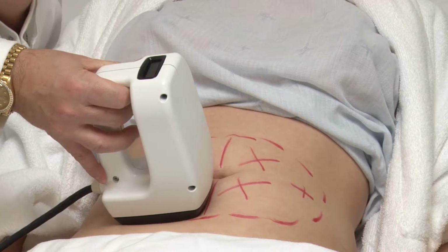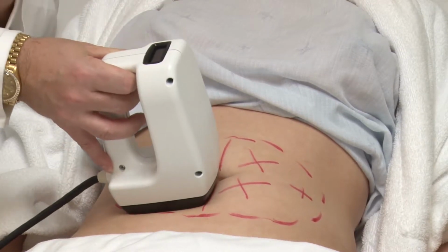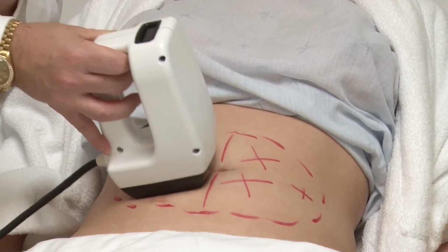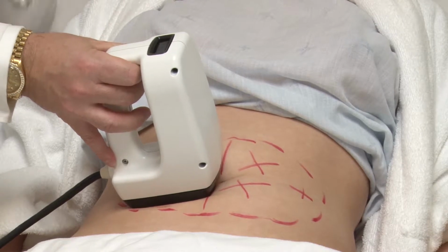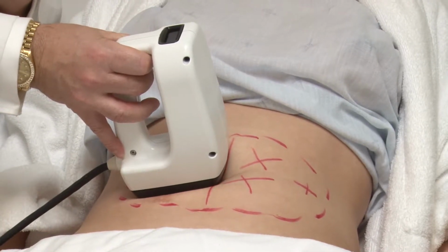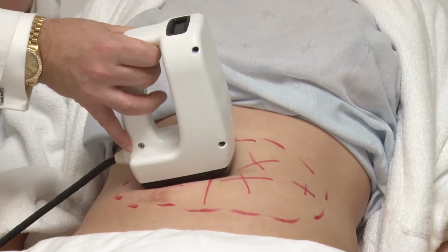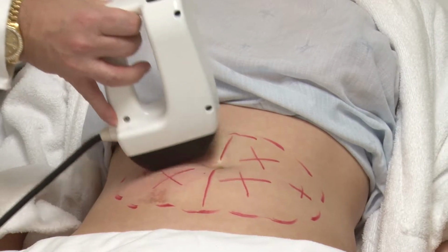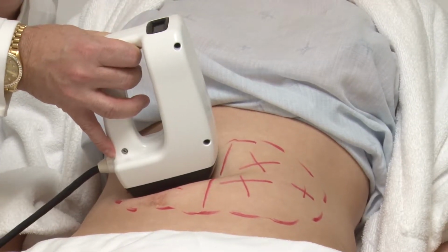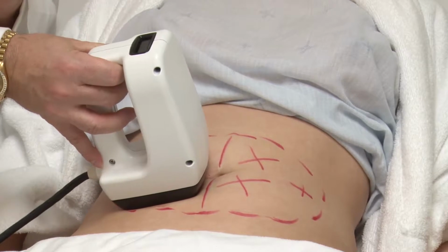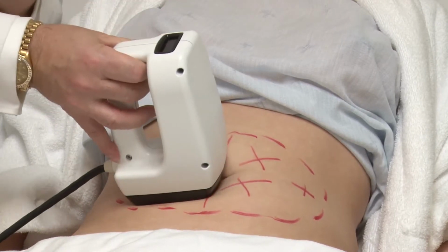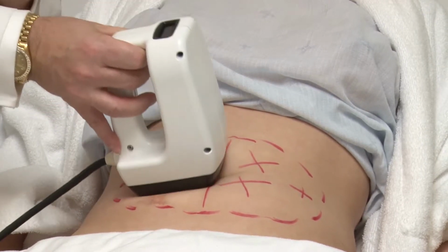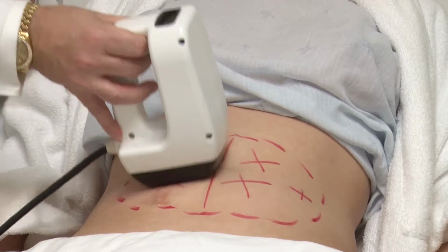Much nicer when it's not so long a pulse duration, correct? Correct. Patients agree that sometimes 2 seconds of sustained heating is too rapid a rise of temperature. So simply take your foot off the foot pedal and move around quickly. We've been treating about 30 seconds. We're about 37 degrees now. We're very close to our endpoint of 40. Now that's not our endpoint ultimately, but we want you to get used to suction coupled thermal stimulation.